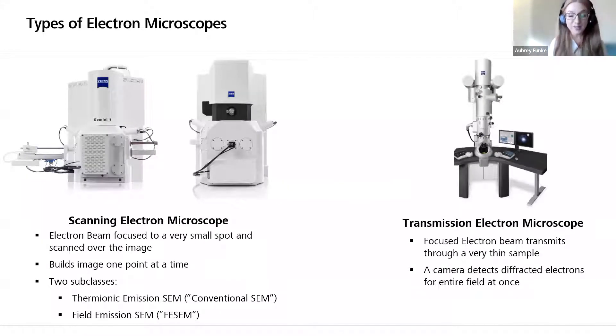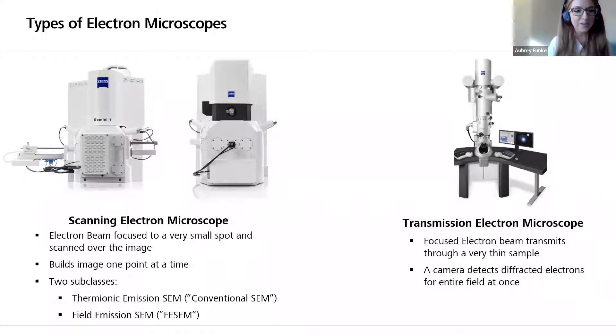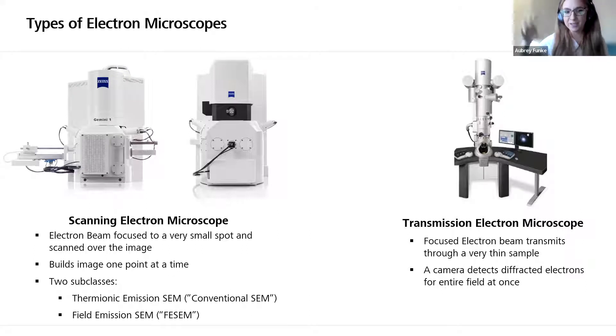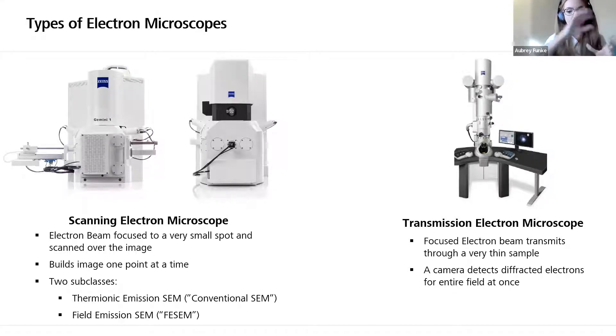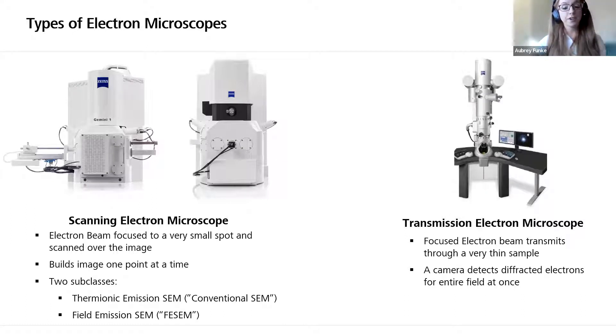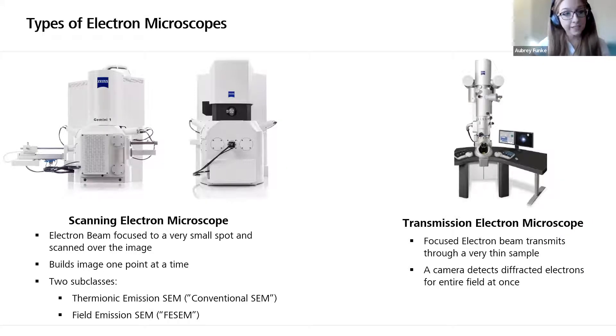Now that we have an idea of what we can do with an SEM, I want to talk about what it is and what it isn't. The scanning electron microscope uses a focused beam of electrons with a really small spot size, and it scans over the sample to build an image one point at a time, line by line, point by point, simultaneously scanning a screen. There are two subclasses: a thermionic emission SEM, or conventional SEM, and a field emission SEM, or FESEM, which is a little bit higher resolution.